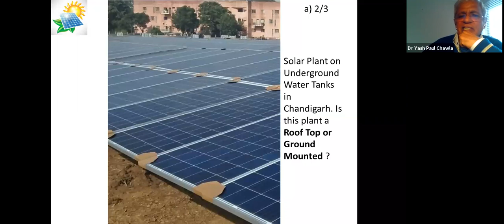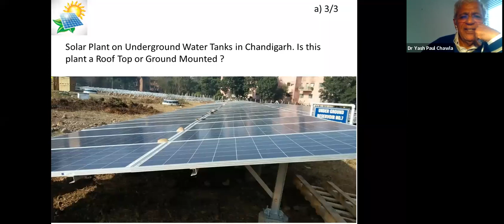The DISCOM wasn't ready to help them, so the petitioner came to us, as a government department also came to us, since people wanted to put this up. The hassle was that if it's a rooftop, you cannot connect it to the grid if it exceeds the connected load. So when we saw there were three transformers available, each of 5 megawatts, we distributed the load, which kept DISCOM happy too. Otherwise the petitioner wanted to take the power a kilometer away to a higher voltage transformer, but we avoided that head-on conflict.